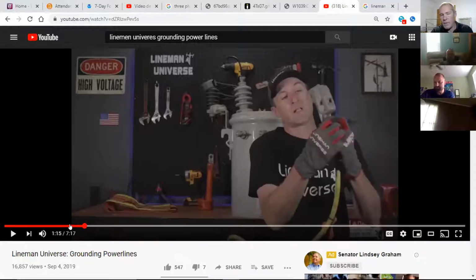The grounding cable is meant for fault current. This thing is rated for up to sometimes 10, 20, and 30,000 amps.